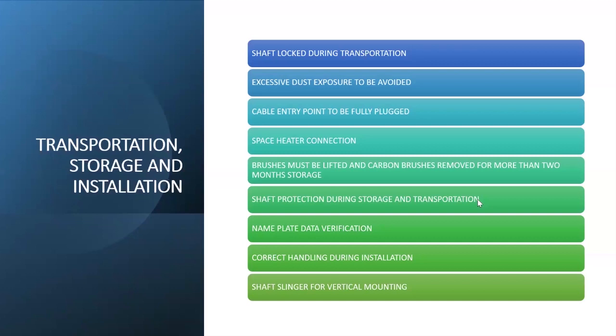for a wound rotor motor, which has slip rings, to prevent any chemical reaction between the brushes and the slip ring, during storage we must ensure we remove our brushes, and the springs are also removed to prevent them from loosening their tension when they are needed. Also, the shaft must be properly protected during storage with denso tape or any other protection chemical which protects the shaft from corrosion.